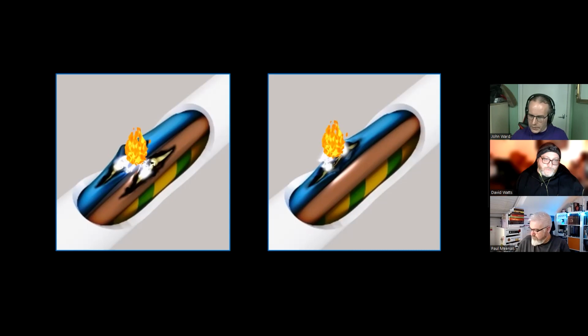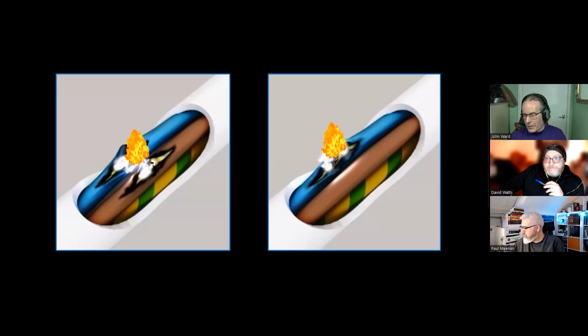What happens with these is that the electrical energy will damage the insulation and carbonize it, which makes it more conductive. That means more current will flow, and then it gets hot, and then it gets more damaged, and it's a sort of endless cycle until flames and fire come out of it. The idea of an AFDD is it detects this before the flames and fire come out, so it would disconnect that before it sets fire to your house or office or whatever else you've got.